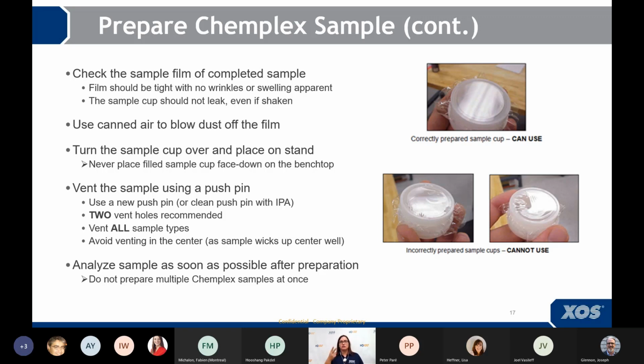And we actually recommend two vent holes, a minimum of two vent holes, for all sample types. Get in the habit of that, so that when it becomes an issue, it won't be. For example, if you're running some isooctane type samples, you can get vapor lock, and what will happen is the film, instead of staying flat, will actually suck up and be concave. But if you use two vent holes, that won't happen. And then of course you analyze the sample soon after preparation.